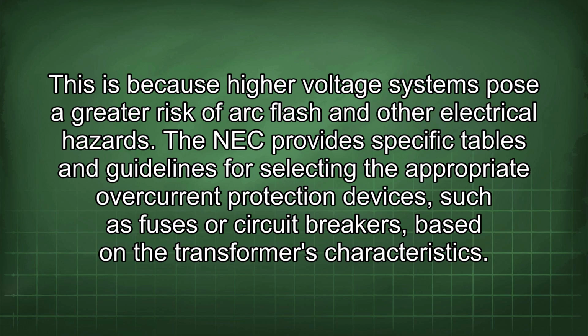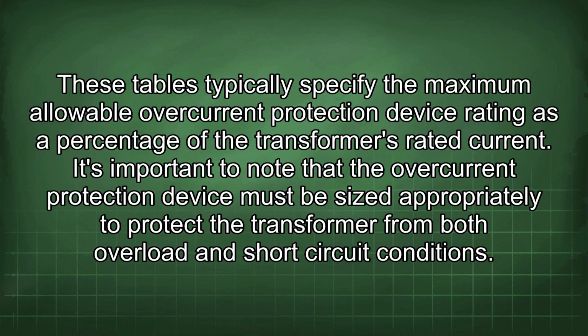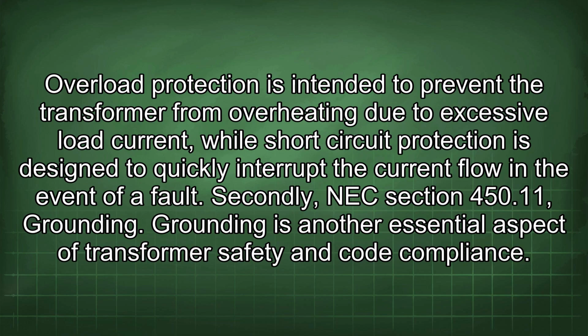The NEC provides specific tables and guidelines for selecting the appropriate overcurrent protection devices, such as fuses or circuit breakers, based on the transformer's characteristics. These tables typically specify the maximum allowable overcurrent protection device rating as a percentage of the transformer's rated current. It's important to note that the overcurrent protection device must be sized appropriately to protect the transformer from both overload and short circuit conditions. Overload protection is intended to prevent the transformer from overheating due to excessive load current, while short circuit protection is designed to quickly interrupt the current flow in the event of a fault.